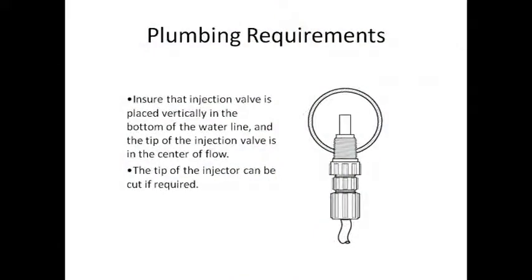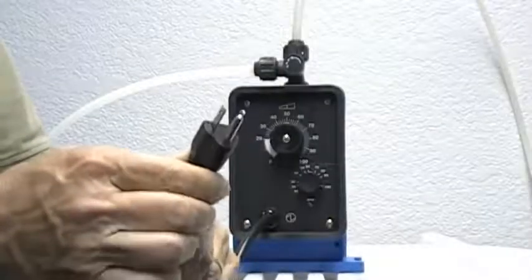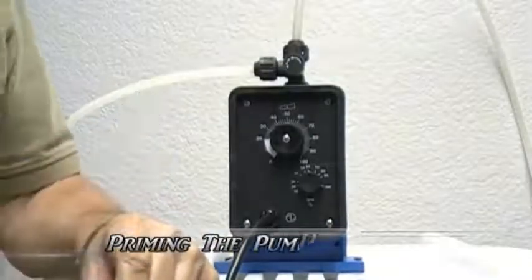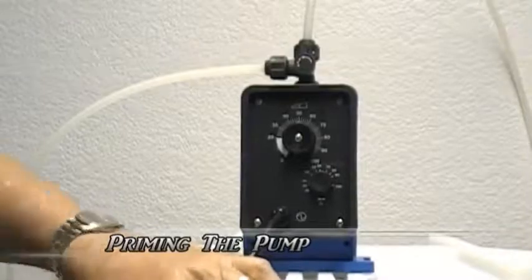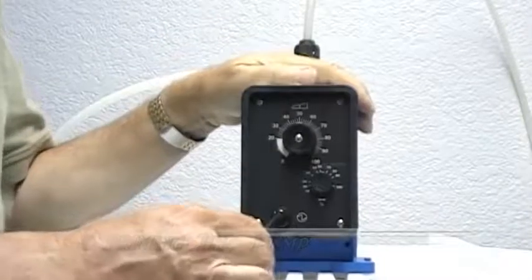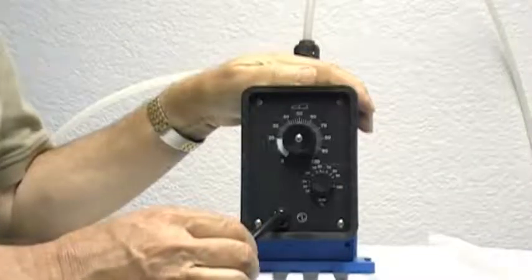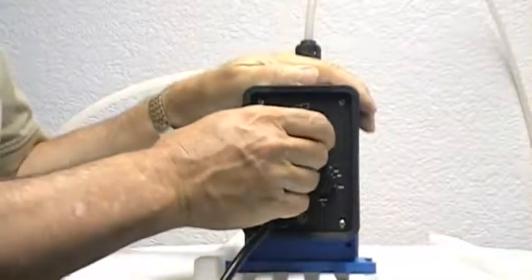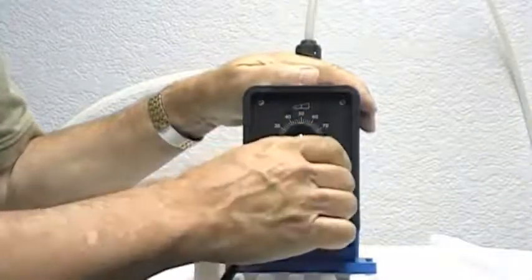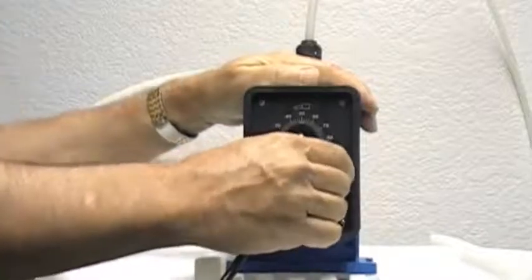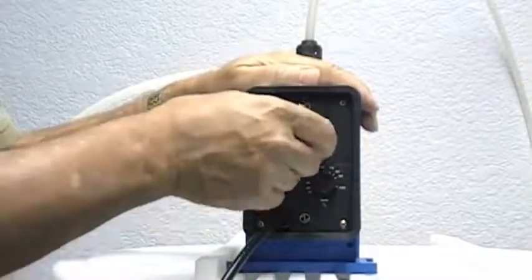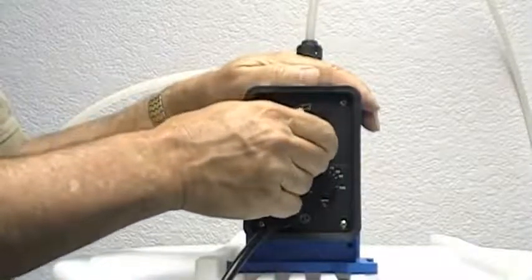Ensure that the injection valve is placed vertically in the bottom of the water line, and the tip of the injection valve is in the center of flow. The tip of the injector can be cut if required. In order to prime your pump, plug the cord into an appropriate receptacle. Please use a surge protector for the power supply of the cord. Be sure that the stroke length is adjusted to 100% and that the stroke rate is adjusted to 100%. Never adjust the stroke length while the pump is not running.